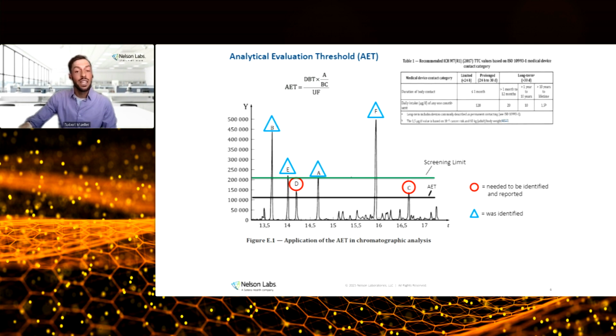If the recalculated AET from the device misuse categorization is below the analytical screening limit, chemicals that should have been detected, identified, and quantified were missed, and the study would not be considered suitable for toxicological assessment. Another potential misuse consideration with a direct impact on the AET is the maximum number of devices clinically used. If a misuse scenario results in more devices being used, the AET would need to be recalculated.